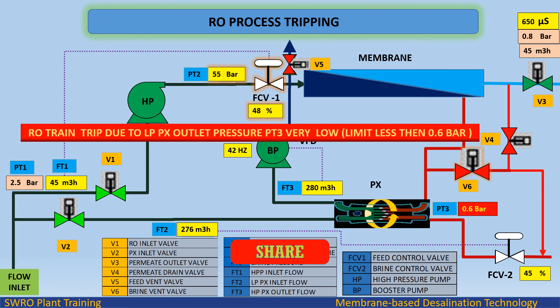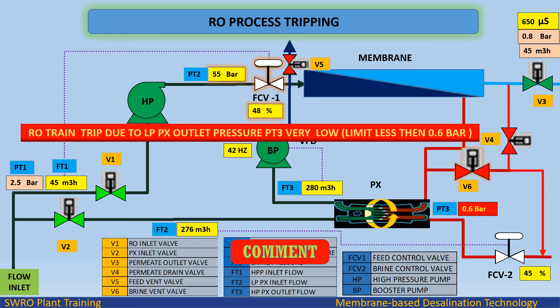RO train trip due to LPPX outlet pressure very low, limit less than 0.6 bar.